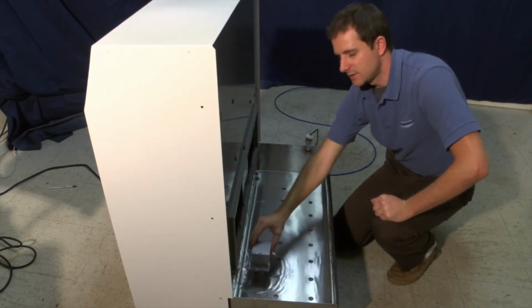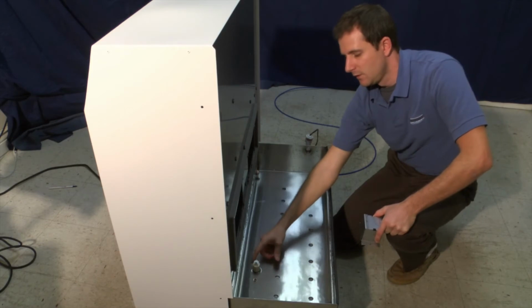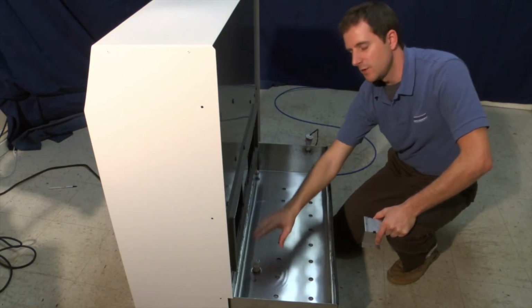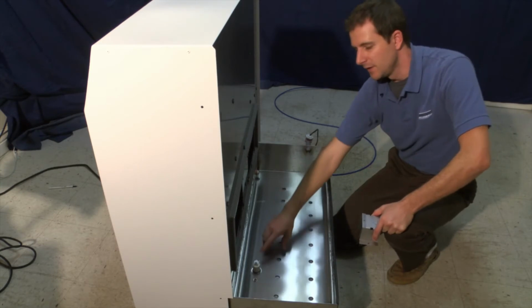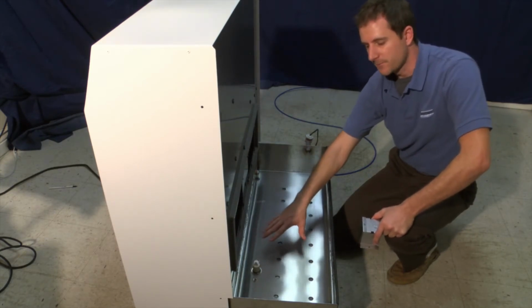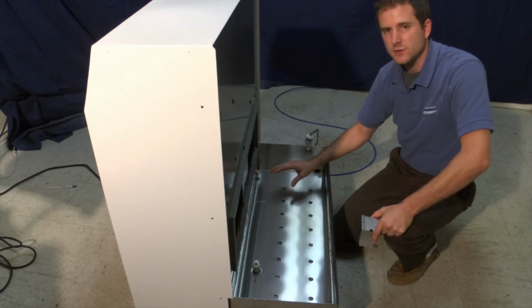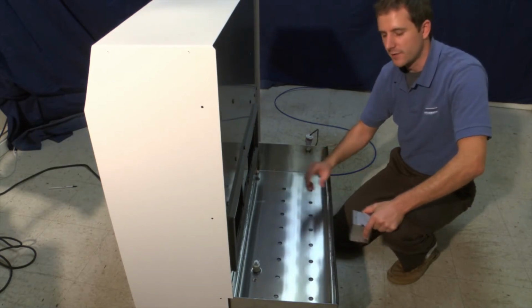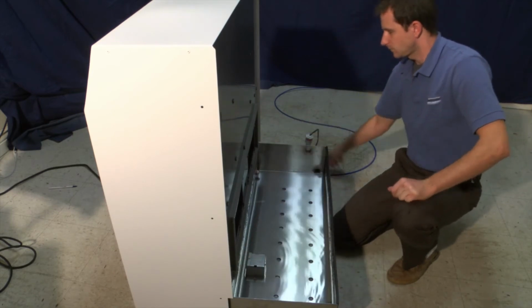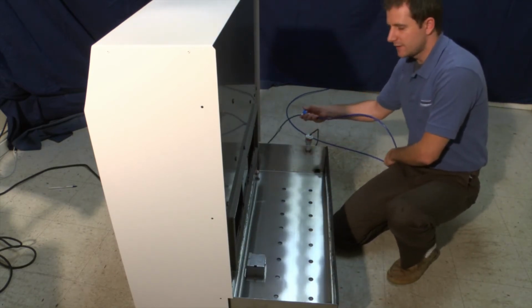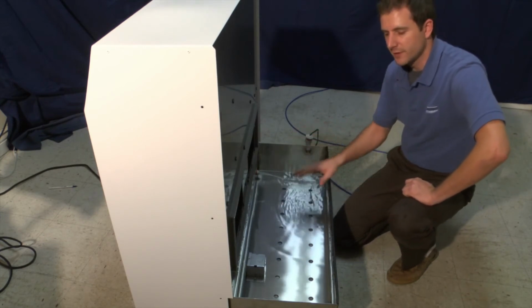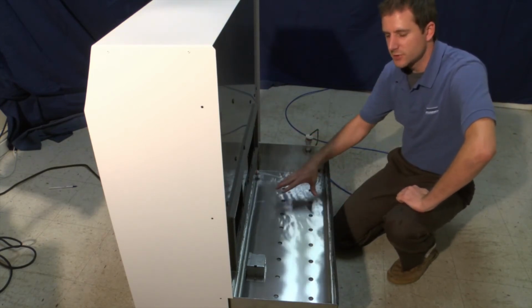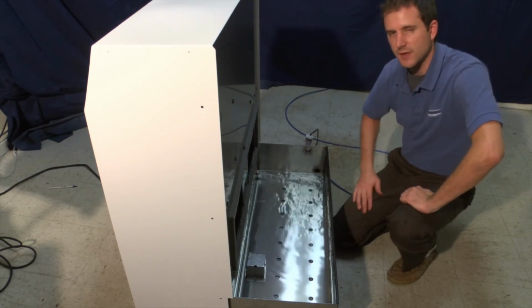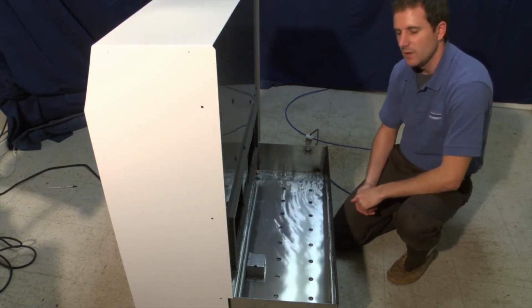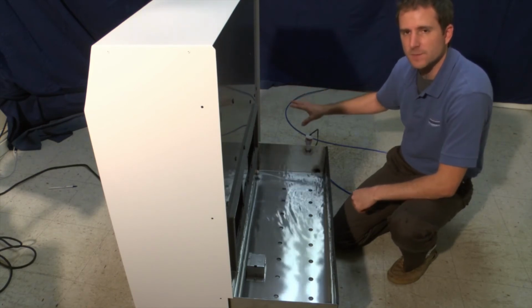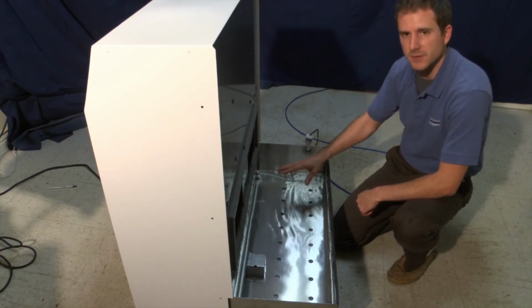Inside the small metal housing is a two-stage float. When the float reaches a first mark, it communicates to the solenoid to refill with water. If the float hits a secondary low mark, it cuts power to the transducers so that they cannot operate without the proper amount of water on them. Activating the water line will show the humidifier refilling with water. Once the humidifier reaches the necessary amount of water, it will allow the transducers to operate again. If the water was to be shut off or interrupted, the unit would shut down completely.